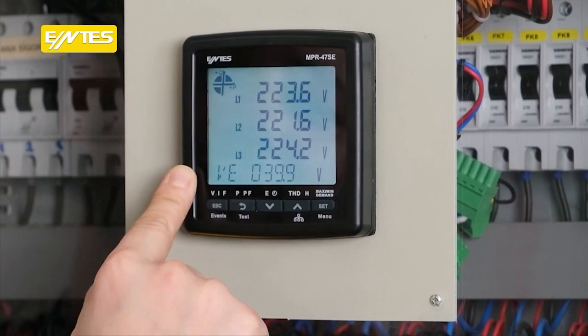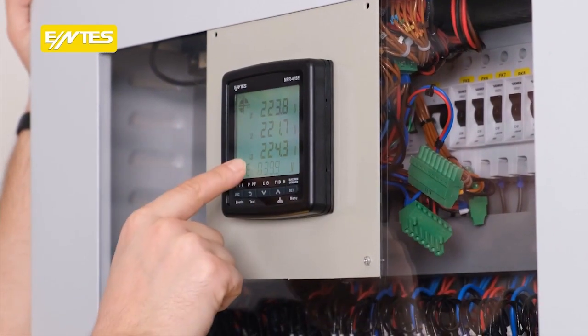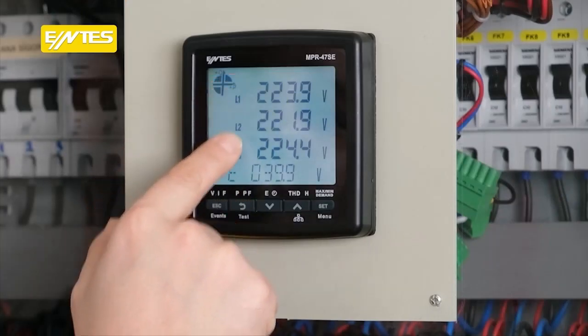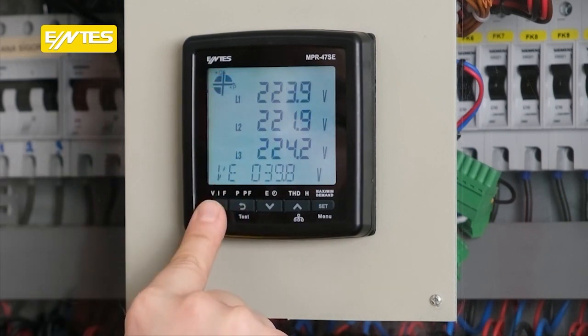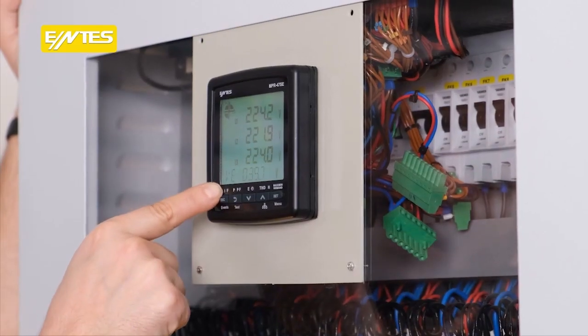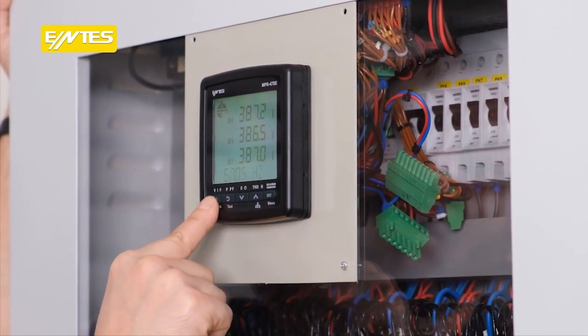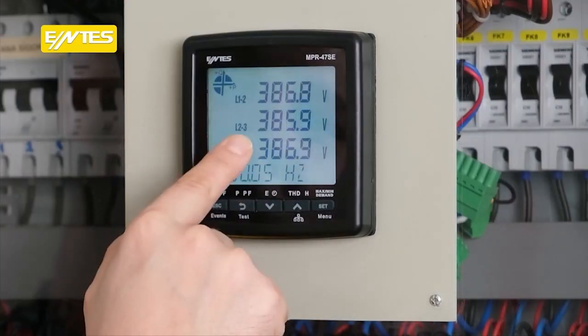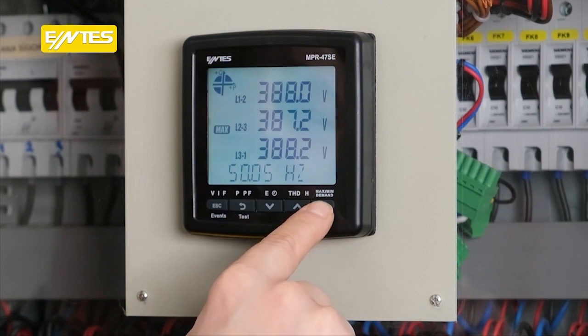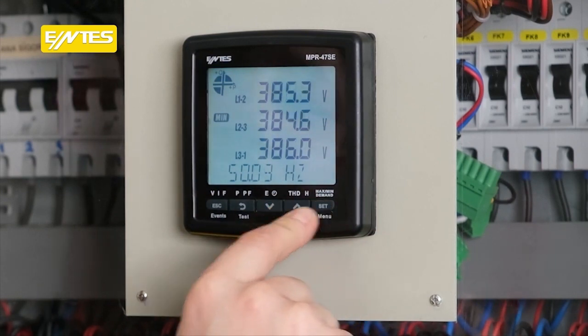Ready to use now. We were greeted here with the phase-neutral measurement screen. Here we see voltage levels measured phase-neutral for each phase. Initially, voltage, current and frequency are shown on the first button. Stepping on it reveals numerous measurements. When pressing set, we can see the min and max values it measures, like this.